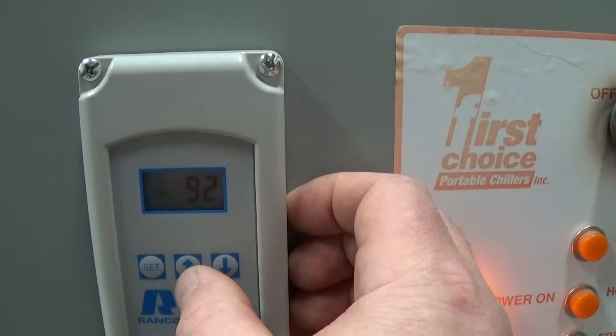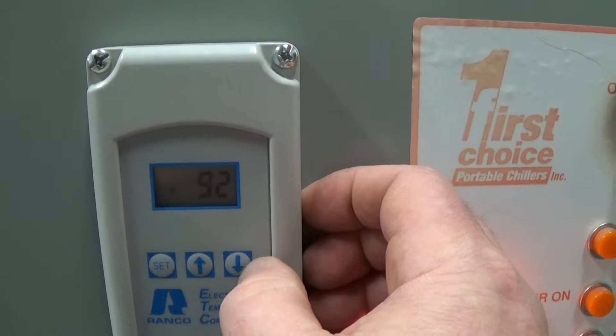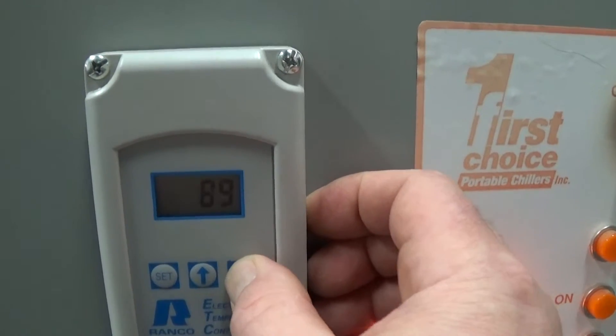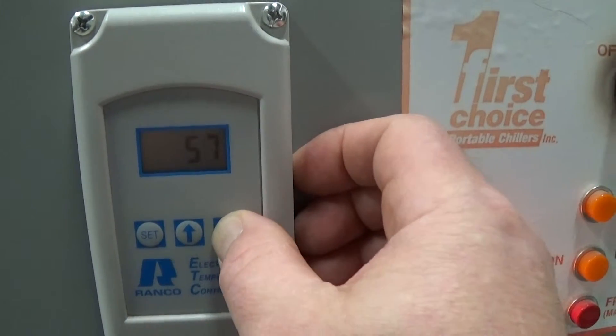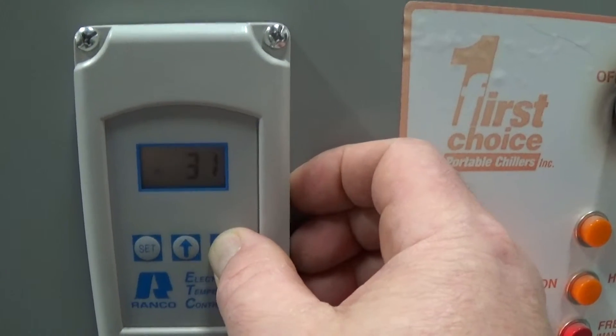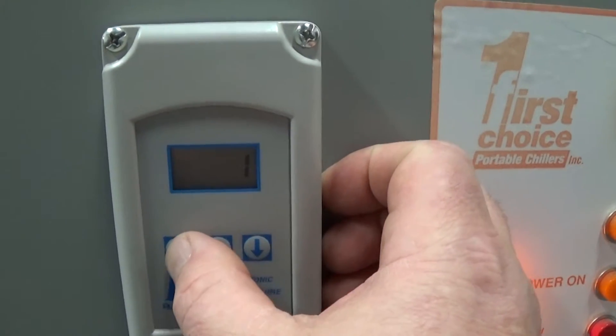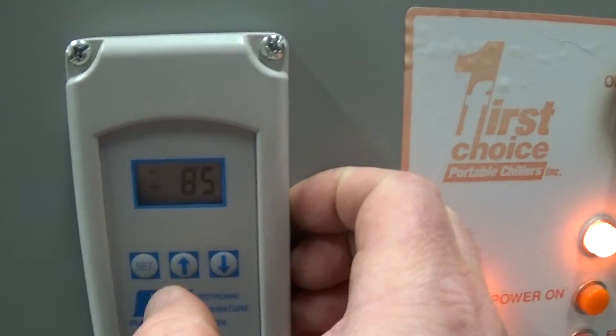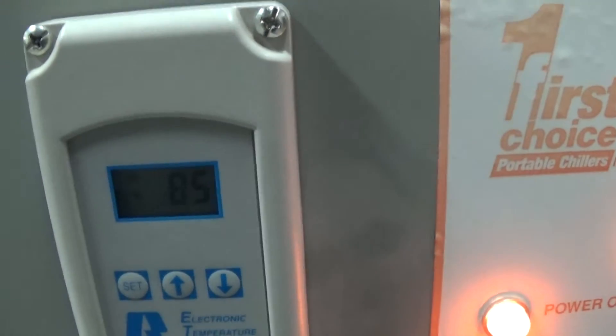The next set point is for the hot gas bypass. We want to set that at 2 degrees above your set point one, so we're going to bring that down to 31. Press set, and we're going to keep the differential for the hot gas at 1 degree. Set, and for this second set point we're in cooling point 2. Press set again, and now we're back to the main screen showing us our current fluid temperature.